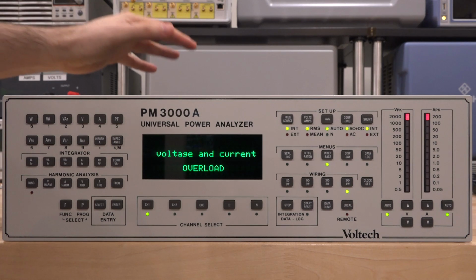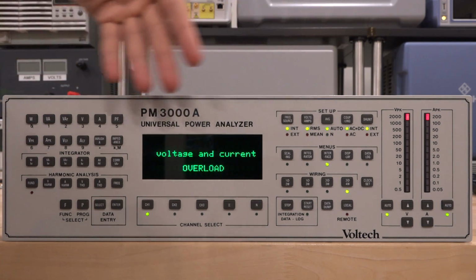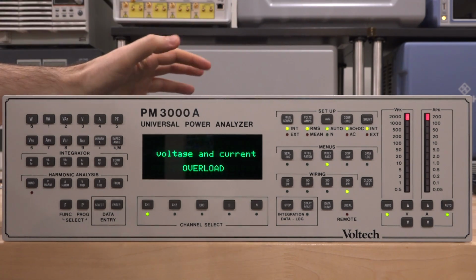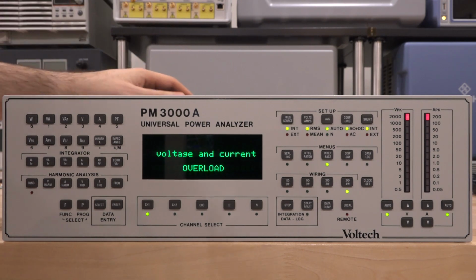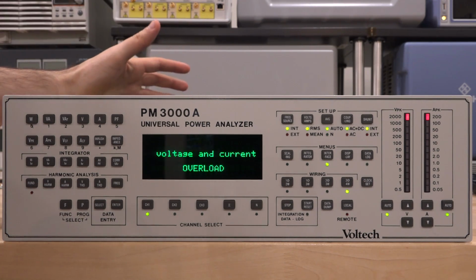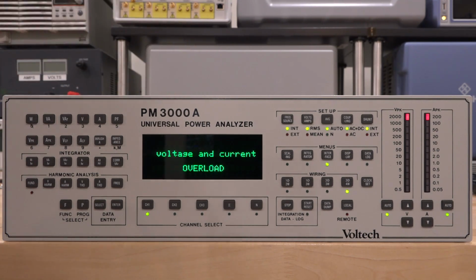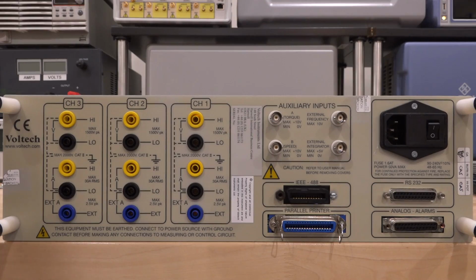Actually, before I open it, let me show you what's on the back, because that's where the inputs are. There's nothing in the front at all, and these are meant to sometimes be in racks and just connected to different instruments for analysis. Hopefully we can fix it, and then we can take a look at some power profiles and behaviors of some of the other things that are in the lab. And here's the look in the back of the unit. As you can see, we have 3 independent channels, 1, 2, and 3 for the 3-phase inputs. And by the way, this can go all the way down to DC, I believe, so it doesn't really have to be an AC signal, but of course it can go to a couple of hundred kilohertz as well.